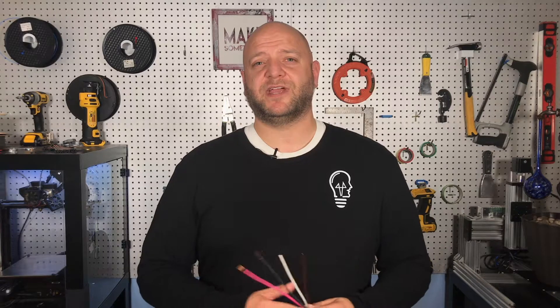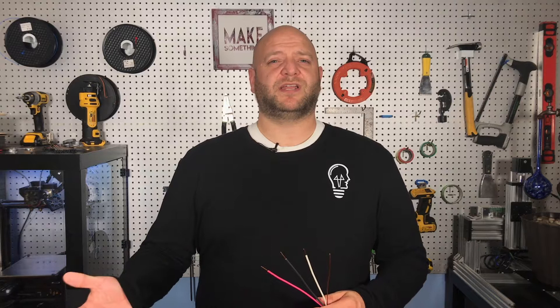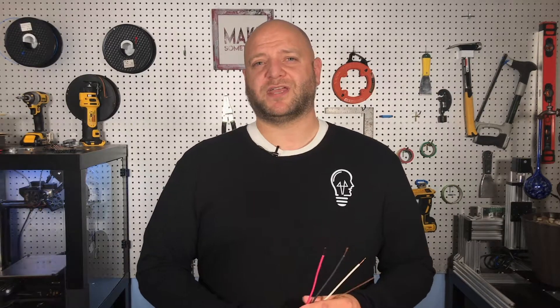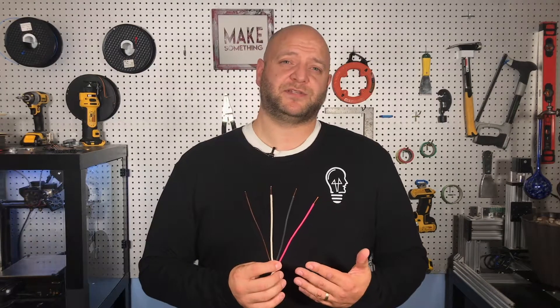I had an interesting experience one time — a friend of mine asked me to troubleshoot a circuit in their basement. When I removed the receptacle to see what was behind it, the wires were connected in a very unusual way. I ended up taking apart every receptacle on that circuit, and what the previous homeowner had done was switch those wires back and forth as they went, which made it very confusing. Some receptacles were wired incorrectly, some correctly, and none of the colors seemed to match.